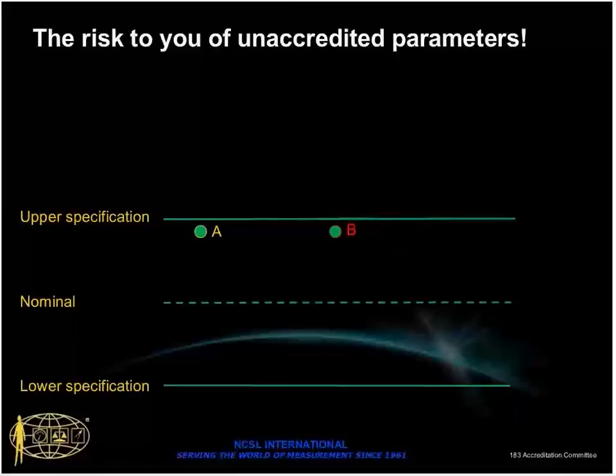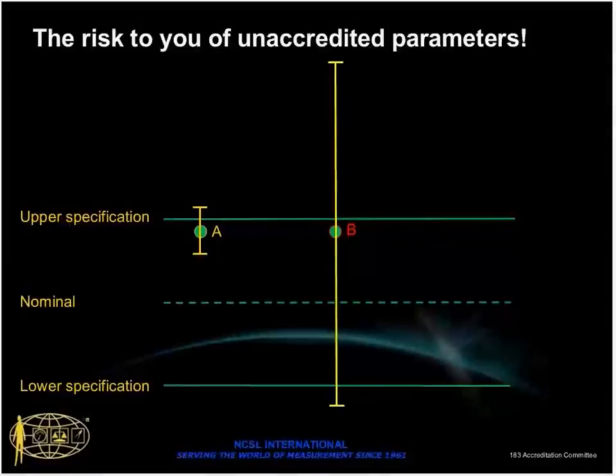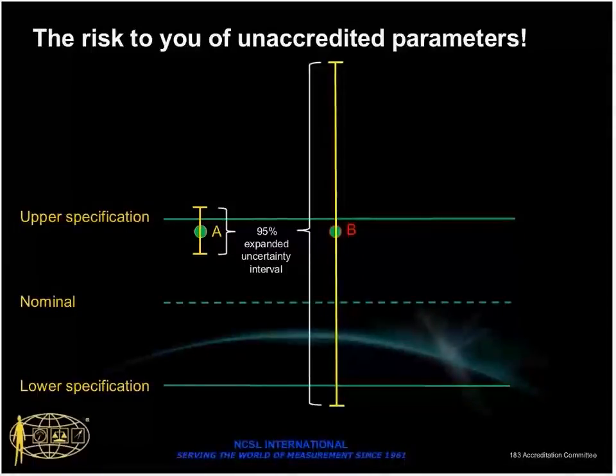These would be examples of a single measurement on a given performance test by two different laboratories. And in this case of our example, you see that they got the same result. So you might say to yourself, oh, okay, well, both say the same thing. This instrument is ready to be used for another calibration period. But you heard us talking about measurement uncertainty before, so let's put that in our example as well. And the yellow areas now show what is the expanded measurement uncertainty. So this is two standard deviations either side of the measured point.